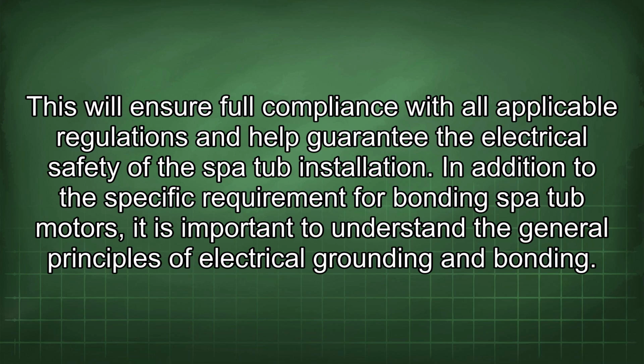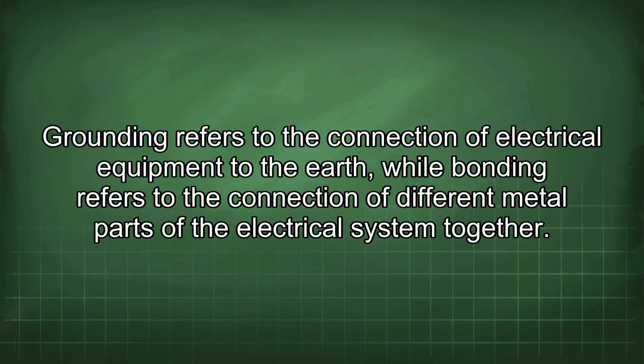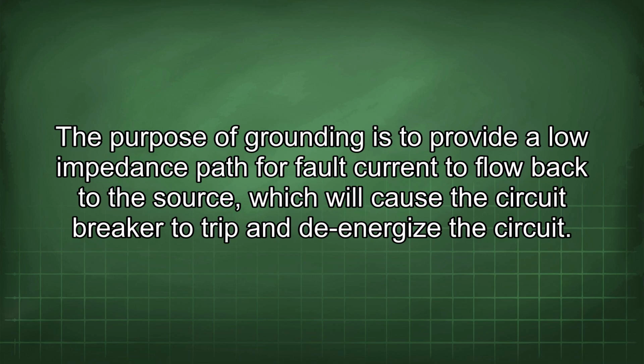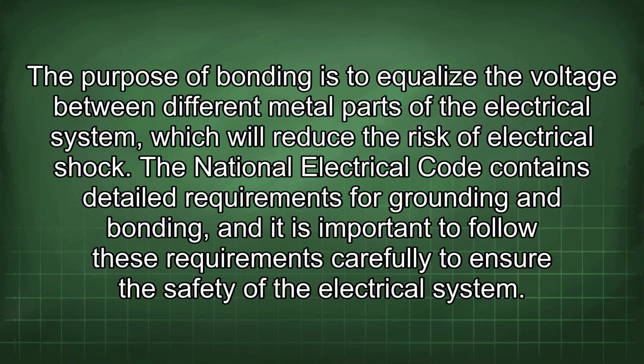In addition to the specific requirement for bonding spa tub motors, it is important to understand the general principles of electrical grounding and bonding. Grounding refers to the connection of electrical equipment to the earth, while bonding refers to the connection of different metal parts of the electrical system together. The purpose of grounding is to provide a low impedance path for fault current to flow back to the source, which will cause the circuit breaker to trip and de-energize the circuit. The purpose of bonding is to equalize the voltage between different metal parts of the electrical system, which will reduce the risk of electrical shock.